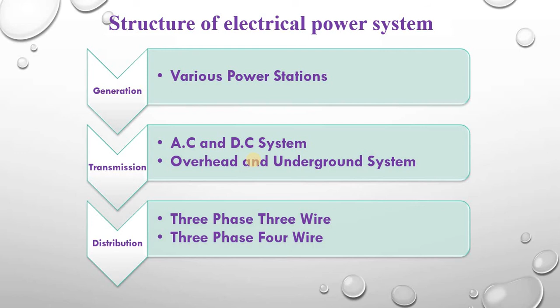So you can see in this diagram the typical AC power supply scheme that is normally adopted universally. Firstly, power is generated at a generating station by three-phase alternators operating in parallel. The generation voltage in India is 11 kV. For economy reasons, this voltage is stepped up from 11 kV to 132 kV with the help of step-up transformers. After that, it is again stepped down to 33 kV by step-down transformers, and that power is received at the receiving stations.